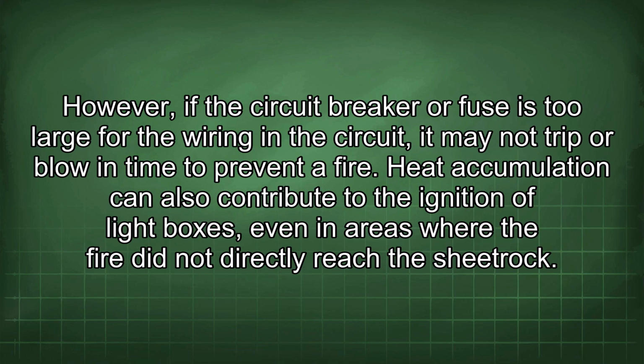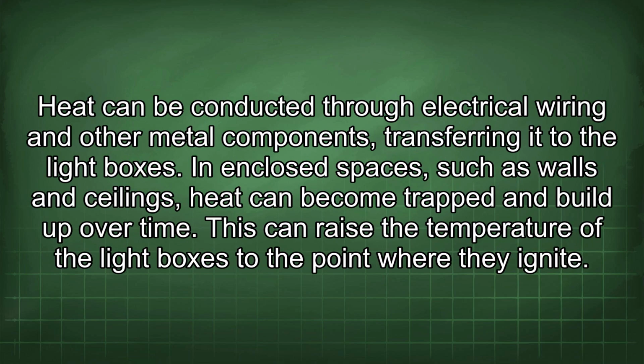Heat accumulation can also contribute to the ignition of light boxes, even in areas where the fire did not directly reach the sheetrock. Heat can be conducted through electrical wiring and other metal components, transferring it to the light boxes. In enclosed spaces, such as walls and ceilings, heat can become trapped and build up over time.